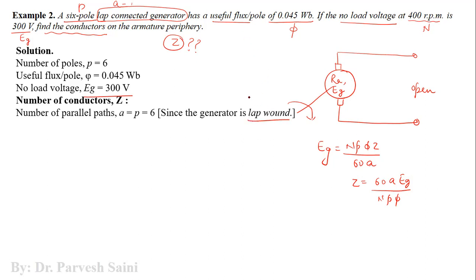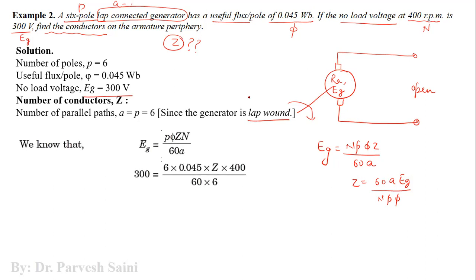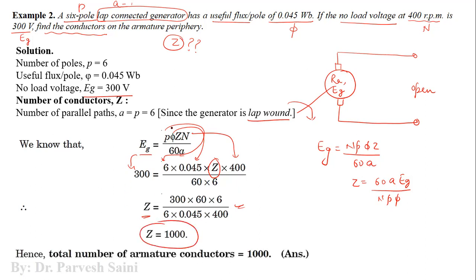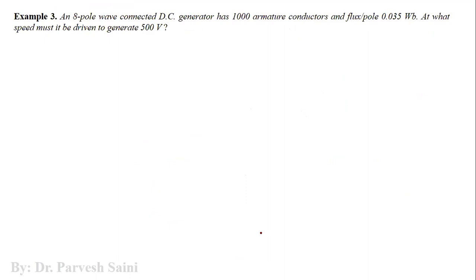Number of parallel paths A = P = 6 because it is a lap-wound generator. By putting all parameters and rearranging the equation to obtain Z, the answer is 1000. To generate 300 volts for a six-pole lap-wound machine with flux per pole of 0.045 weber rotating at 400 rpm, 1000 conductors are required.